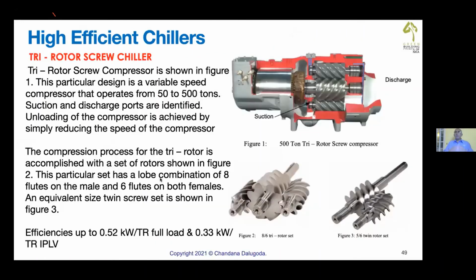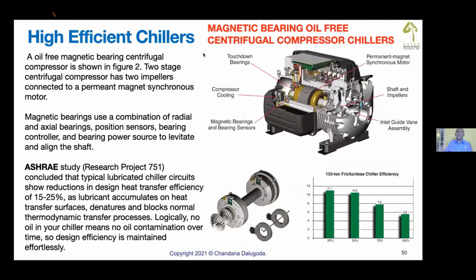And just to give us some idea, there are so many chillers, so many compressors in the world, but there are two categories that give high performance. One is the tri-rotor screw chiller that will give very good efficiency, 0.52 full load. And another is the chiller with magnetic bearing, that is a high efficiency chiller. But both of these are quite efficient in part load applications. So we've got to be very careful how we apply these things.